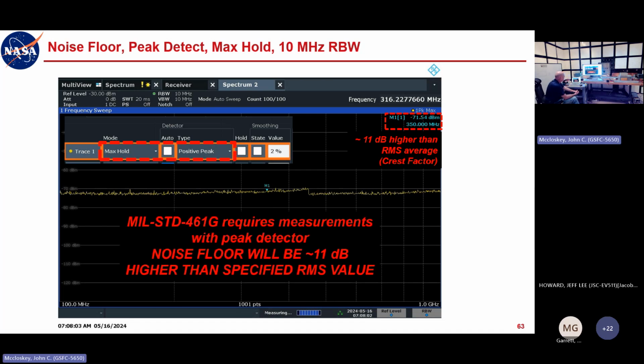But the point here is MIL standard 461 requires measurements with a peak detector. So your noise floor will be about 11 dB higher than the specified RMS value in the manual for your measurement device. If you're looking at low level signals and want to determine what your noise floor is and the range of signals that you can actually measure, you need to take this 11 dB number into account. So I think this is a very important thing. That's why I thought it was worth spending a little bit of time on, so that you understand where this 11 dB number comes from.